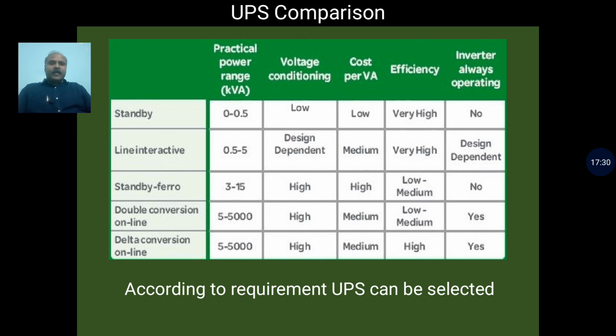Similarly, delta conversion online can be considered for three phase or huge power uninterrupted output and industrial purposes. Delta conversion UPS is a modern innovation that eliminates the disadvantages of the traditional double conversion online UPS. The enhancements are based on having a delta inverter. So it consists of a delta inverter, which is why the name implies delta conversion, which is nothing but an online UPS. It also provides high efficiency. So that's all for now. Thanks for watching.